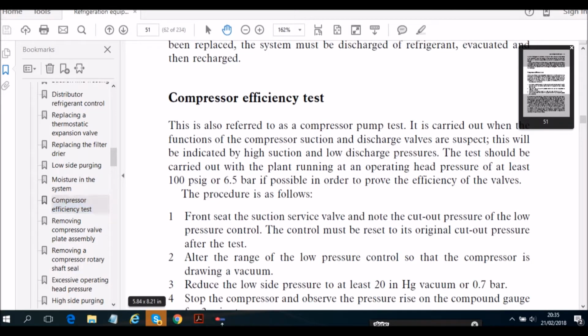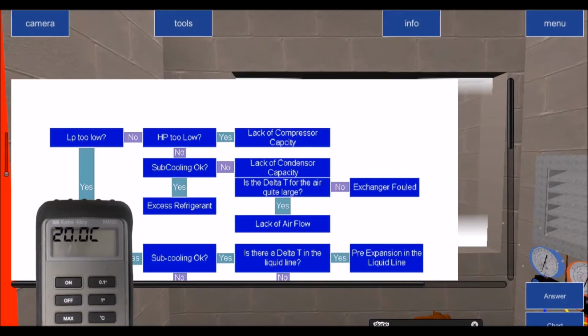Now, getting back to this fault number two, again, we start at the very beginning. Because we are getting a room temperature of 10 degrees, the customer has called us. The room temperature should be 2 degrees. So first thing we ask ourselves is, have we got normal evaporating temperature or suction pressure? And again, we use our rule of thumb, 5 to 10 degrees of a difference.